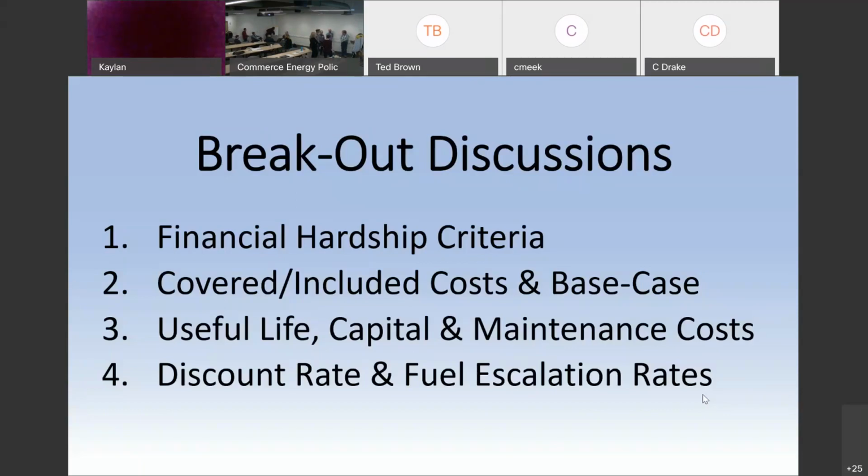Well, I was going to say, at Fred Hutch, we have a table of all the equipment that's in our facilities, and we've assigned useful lives out of engineering sources, and we're constantly going through and evaluating that piece of equipment. We don't just replace it because it's at the end of its useful life. We judge, is the equipment running correctly? So I think it has to be analyzed as to whether, as a piece of equipment gets closer to what the book says is the useful life, is it really the end of the useful life, or can that thing be extended?